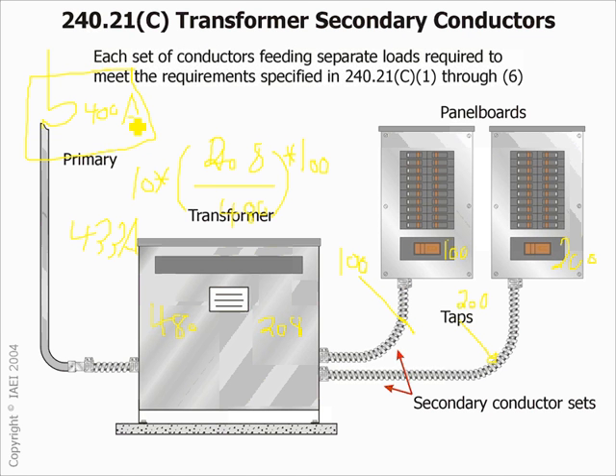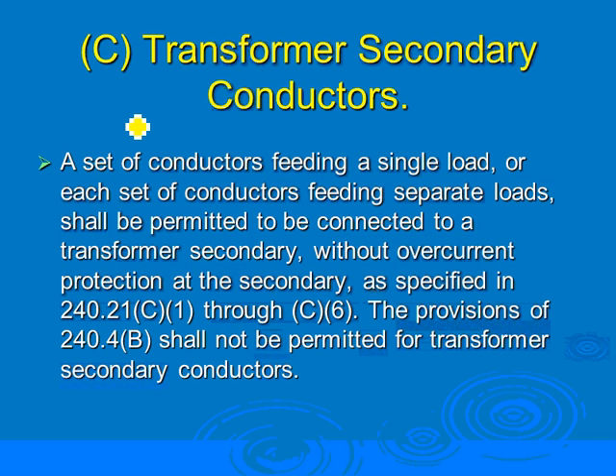When you size the primary with the transformer, what do you do? You're going to take the full load amps of the transformer, multiply it by 1.25, and then you size your primary, right? So that's what we typically do. If you are to adhere to these rules, that number that you came up with cannot be higher, and I hate to throw numbers here, that number here cannot be higher than this ratio, basically. But here's a challenge. What if it's higher? What if you need it higher? Maybe you're feeding 4 panels or 5 panels. What if it needs to be higher? What do you do? You just put a bigger conductor here. Instead of whatever 100 amp cable here, you can put a 200 amp cable to that panel, if that makes sense. So that's a few rules about the transformer secondary conductors.